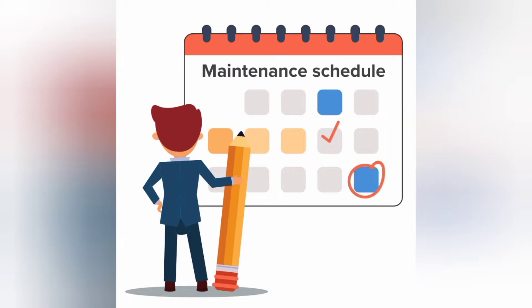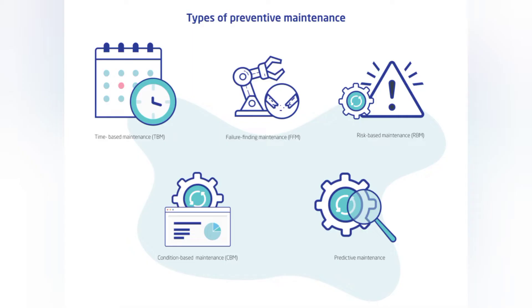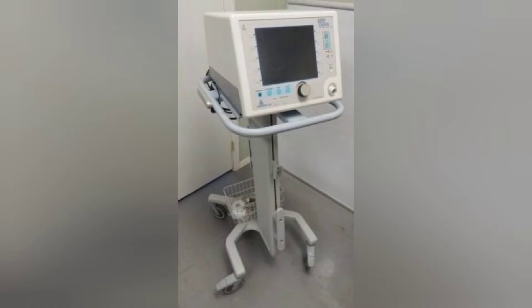Generally, all medical equipment requires at least two PMs in a year. Some critical equipment may require four in a year. Preventive maintenance should be done in ideal steps, one by one. The very first step is physical examination — when you go in front of any medical equipment, the very first thing to do is to observe the equipment physically without switching it on.